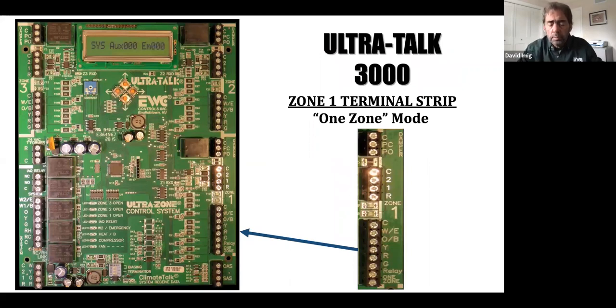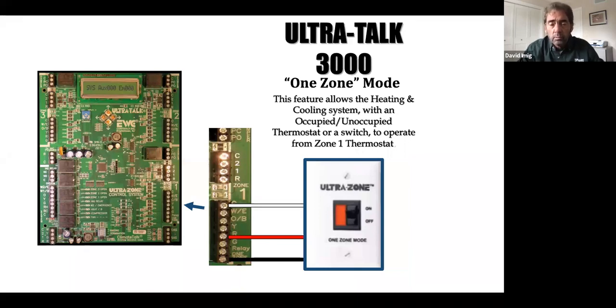Zone 1 terminal strip, the dry output does have a couple of other features that the other zone terminals do not have, and that is the one zone mode. This gives me the ability to tie in our particular accessory and utilize the ability for this to operate in one zone mode. Why would I do that? If I'm going away for a period of time, long weekends, vacations, rather than go around and switch all thermostats, either change program or set them down or turn them down, I turn this switch, that takes it out of zone mode, and the entire structure and dampers operate off the zone 1 thermostat. When I return, when I want to put it back into zone mode, all I simply do is turn the switch off.